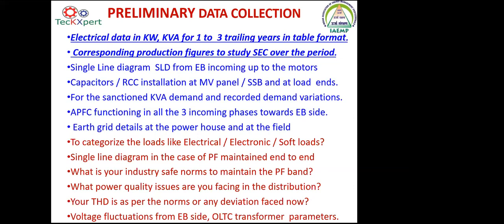Here, in many industries, once you enter, we know if it is a highly fluctuating load, what is done in the industry. See, we have recently worked with a very big engineering group industry. In fact, this industry has an active filter, reactor-coupled capacitors, everything. After our energy audit, we suggested that more than 20% of their load be done for load compensation. They revisited the load compensation topic, and they reduced the excess redundant capacitors in the powerhouse and the SSB, and they were able to save almost 4 to 5% of energy in this aspect.